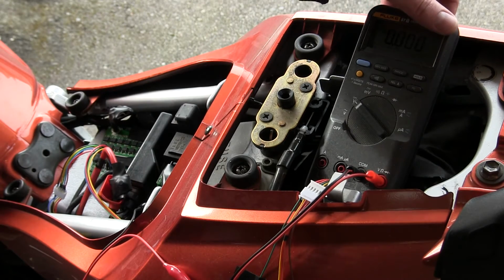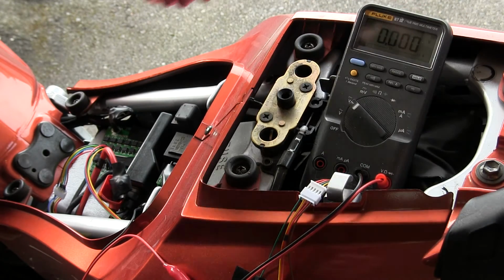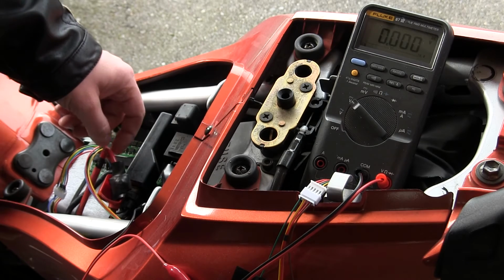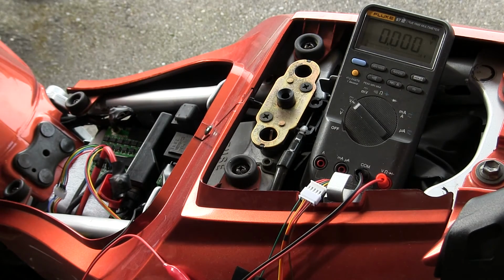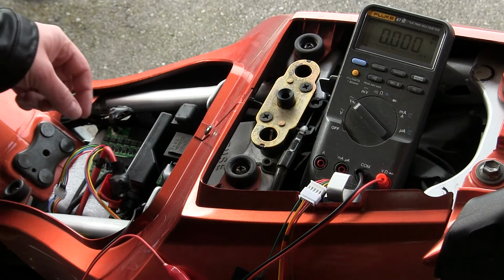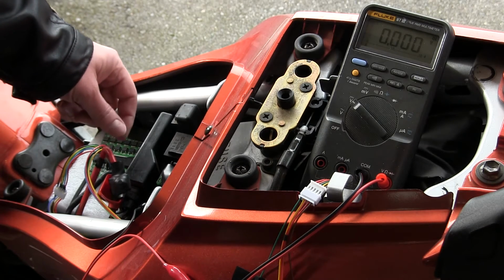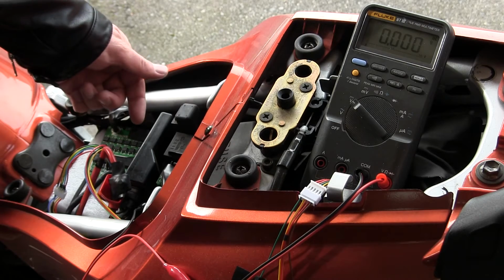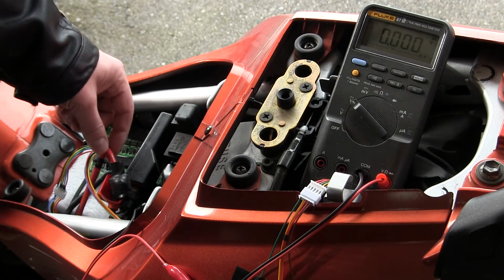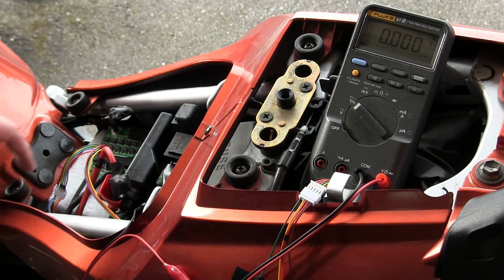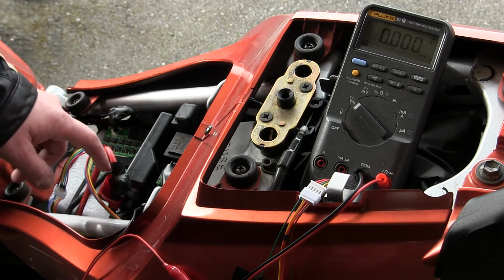Because this wire is 8-gauge, it's not really designed to handle 200 amps for a long period of time, but it will handle 200 amps for a short period quite happily. I should see a significant voltage drop here in this wire and these connectors.